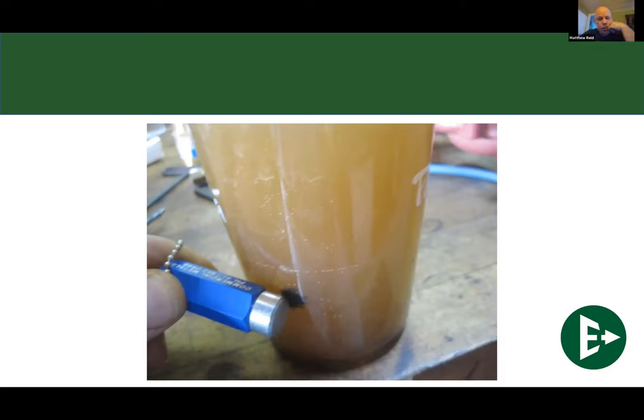Now, there are two places in your system where magnets are going to be, and if you don't put two in there, you're going to have problems. The first one is in your pumps. There's already a magnet inside that rotor to keep it spinning, especially with these variable speed pumps that are reasonably expensive. You want to protect that because they are susceptible to magnetite. If you're pulling one of those rotors and it's completely covered in sludge, that sludge is caused by magnetite getting stuck to that rotor. That can be a pretty expensive repair.